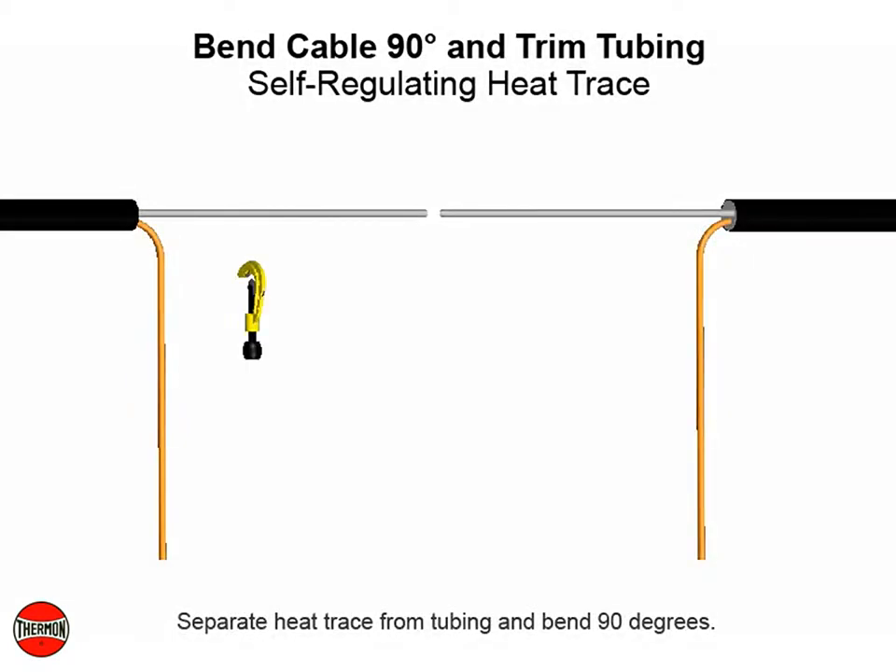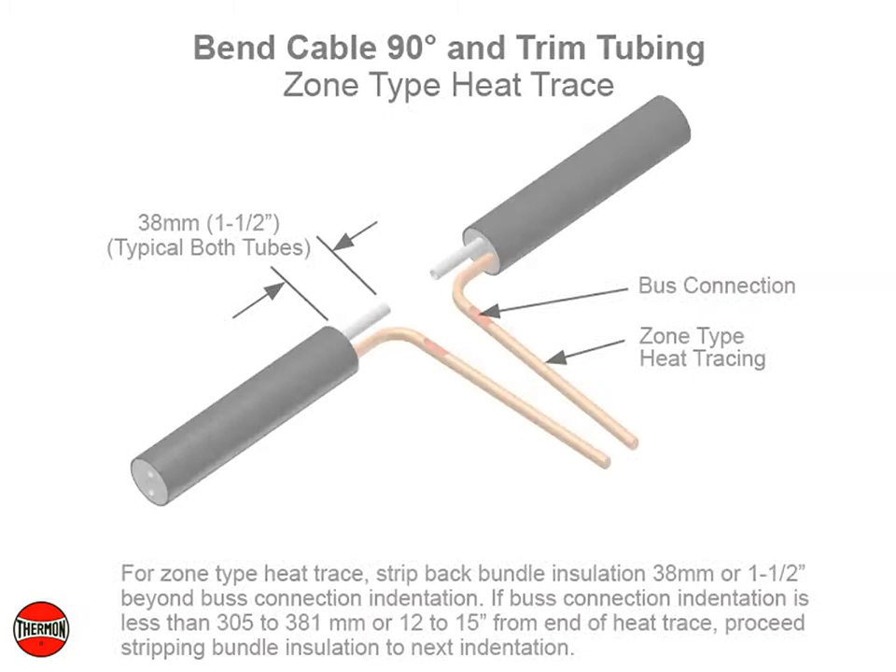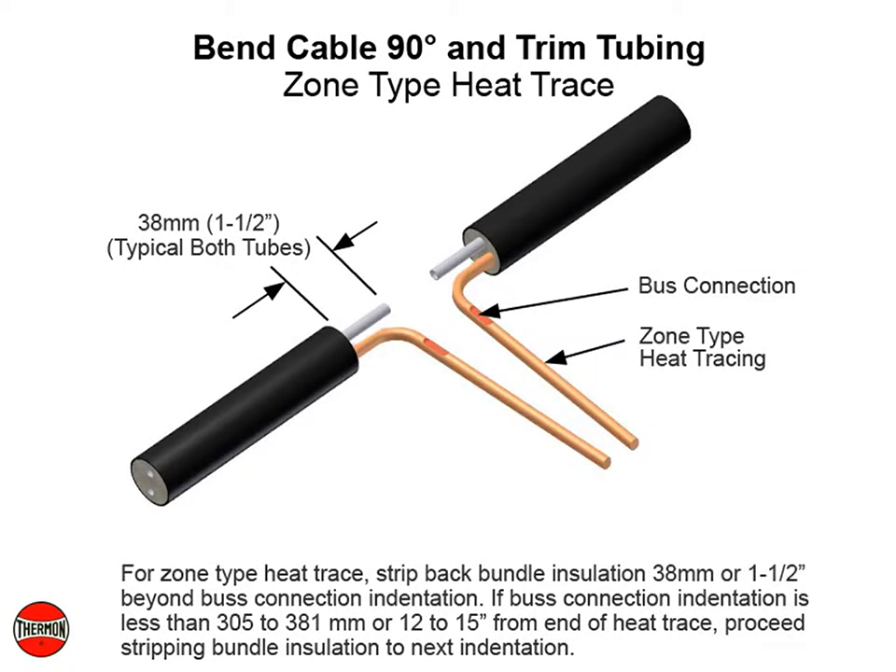Separate heat trace from tubing and bend 90 degrees. For self-regulating heat trace, trim tubing to within 38 millimeters, or 1½ inches, of end of insulation. For zone type heat trace, strip back bundle insulation 38 millimeters or 1½ inches beyond bus connection indentation. If bus connection indentation is less than 305 to 381 millimeters or 12 to 15 inches from end of heat trace, proceed stripping bundle insulation to next indentation.